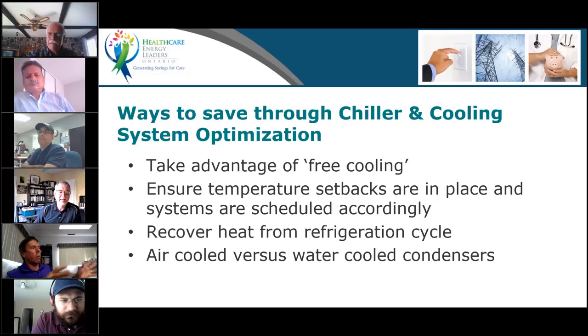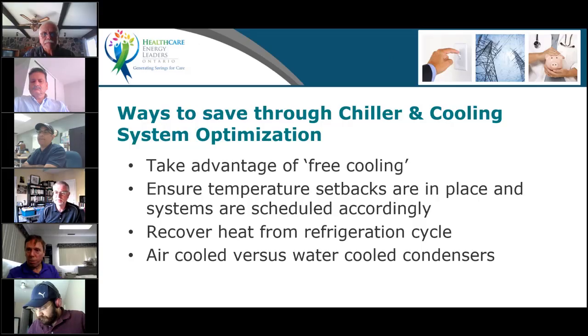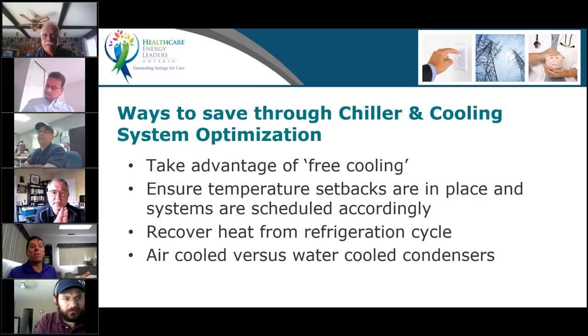So those are things to keep in mind when you have heat recovery. For example, in Quebec, heat recovery chillers are very common in hospitals because it's actually economical to run them, because gas is more expensive than it is in Ontario and electricity is actually cheaper. And with the COP of the heat recovery chiller, you'll see that in many hospitals. And obviously, because electricity has a lower greenhouse gas emission factor, you actually save greenhouse gases by going with your heat recovery chiller.